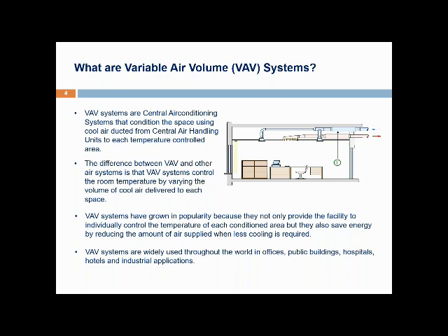This is different from constant air volume systems, which supply a constant volume of air to the space. VAV systems have grown in popularity because they not only provide the facility to individually control the temperature of each conditioned area, but they also save energy by reducing the amount of air supplied when less cooling is required. They only supply as much air as required to meet the cooling requirement. They have become very popular worldwide — many large offices, public buildings, hospitals, and hotels use VAV systems. The principles of VAV are also well applied in industrial applications.